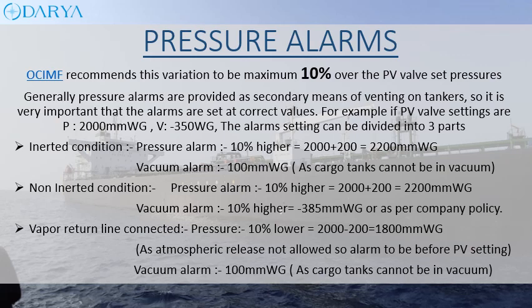OCIMF recommends pressure alarm variation to be a maximum of 10% over the PV valve set pressures. Pressure alarms are generally provided as the secondary means of venting on tankers, so it is very important that alarms are set at correct values. Examples of pressure alarm settings are given under three conditions: inerted condition, non-inerted condition, and vapor return line connected condition.